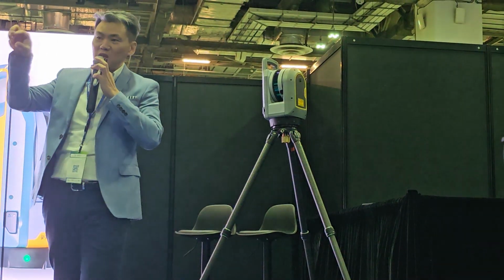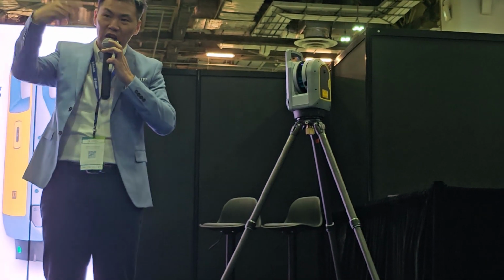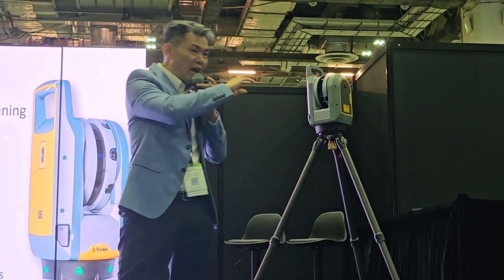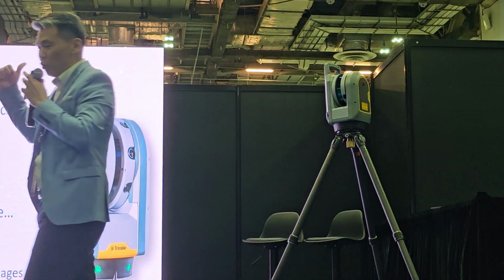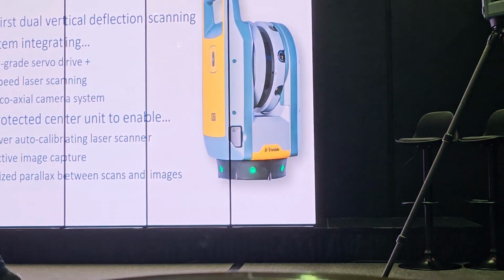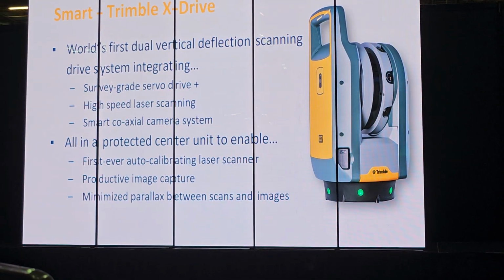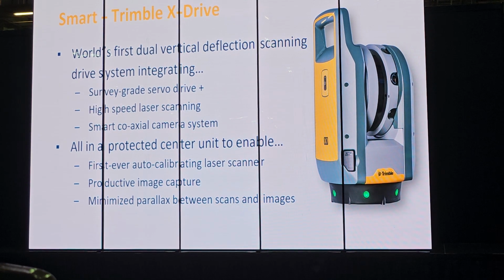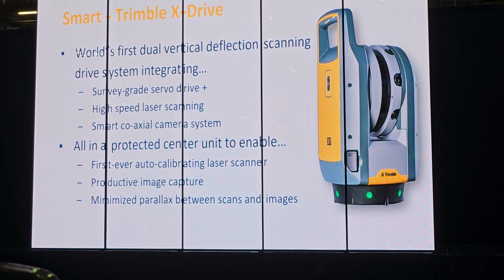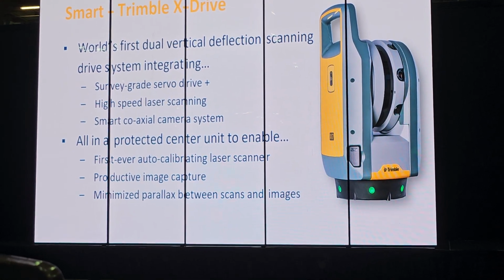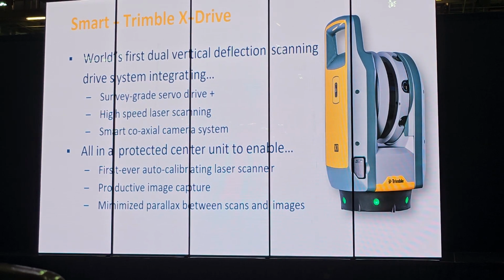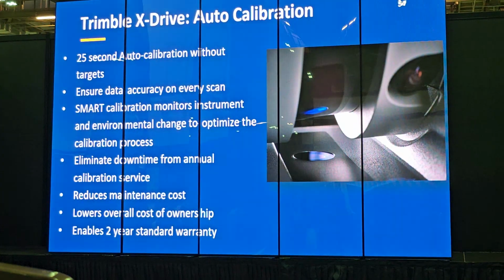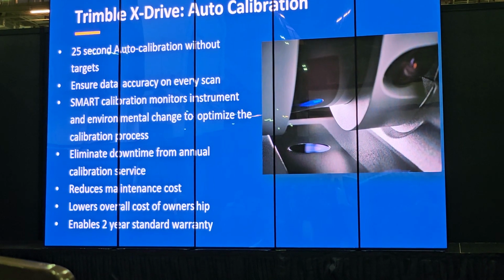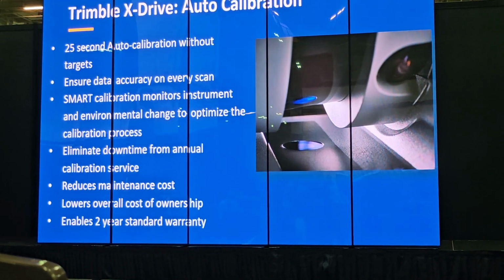The scanner you can see that you use today, you can see the head is turning, but you cannot see the head here. This is what we call X drive. We pack the laser scanner, we pack the camera inside the drive. So inside this drive, there's a level compensator. There's also other technology that enables us to do auto calibration, right? Inside this drive, as I mentioned.